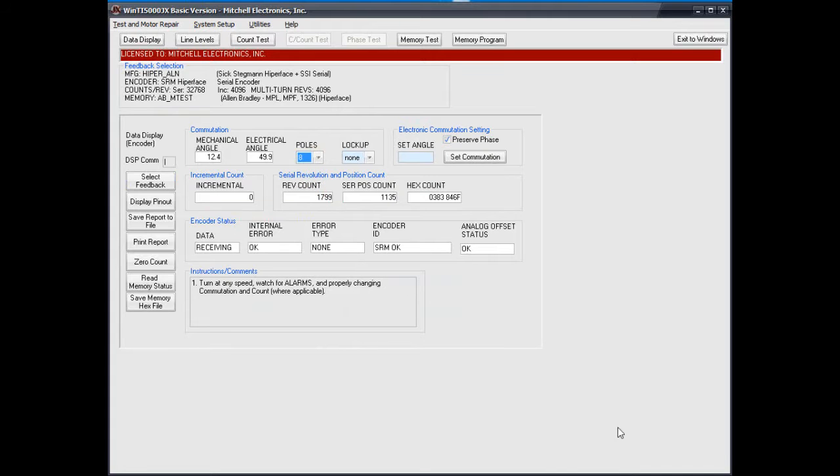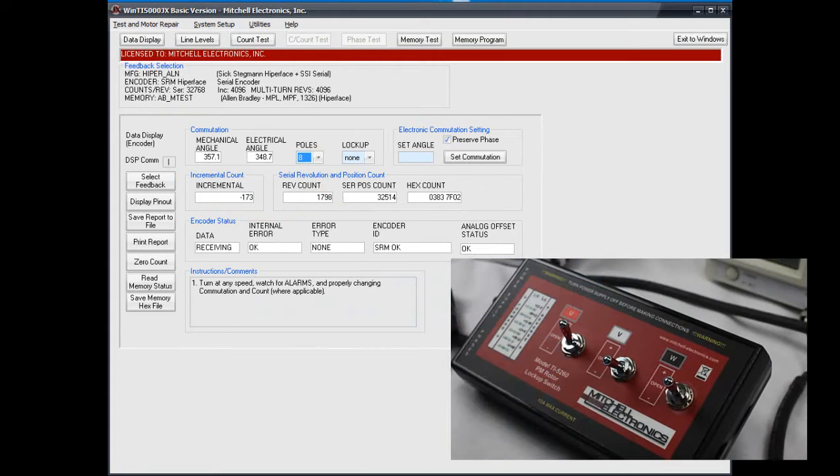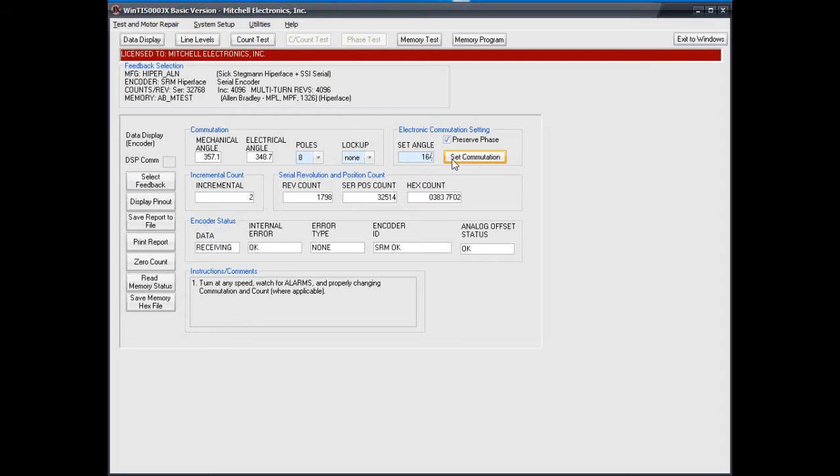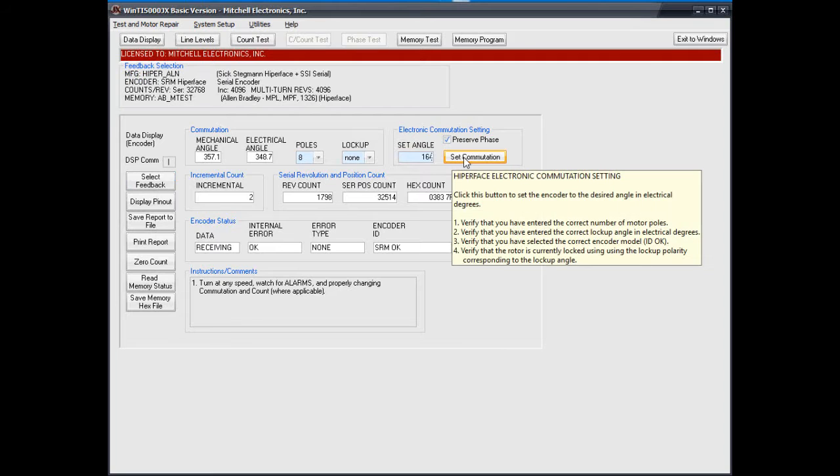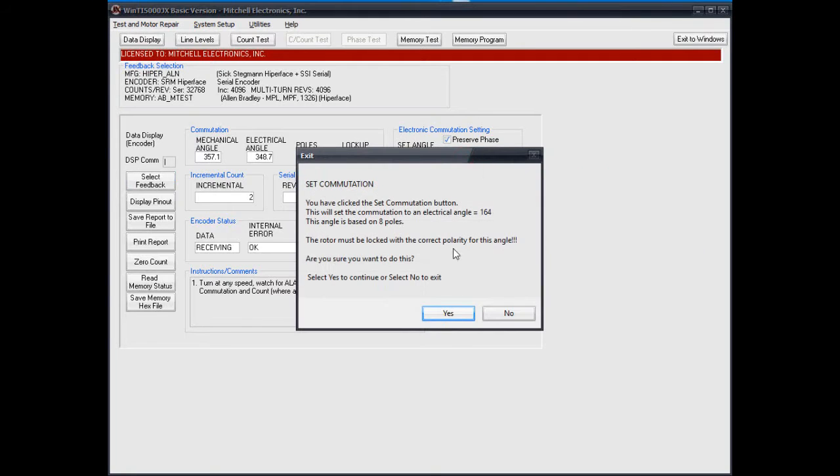Then lock the motor and type in the angle that you wish to electronically align to. Press Set commutation and the encoder will align to the angle provided.